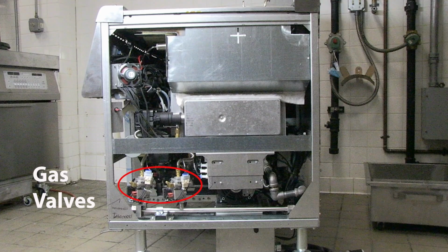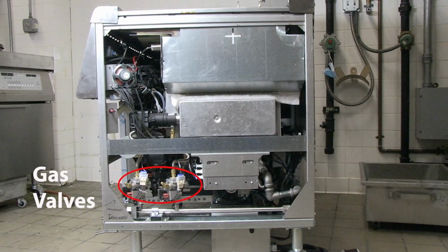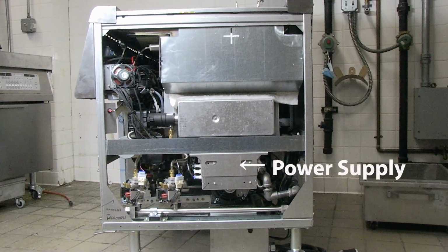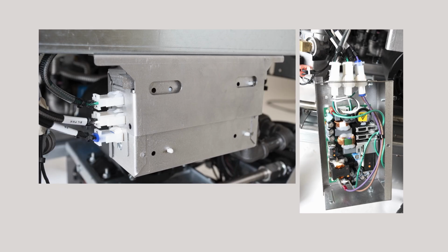Behind the removable sides, the gas valves are easily reached. So is the power supply for the vat. Each vat has a 24-volt DC power supply that runs the HCB, spark modules, and gas valves. The power supplies are suspended from brackets beside each vat. They rest on pins and are easily lifted out for service.